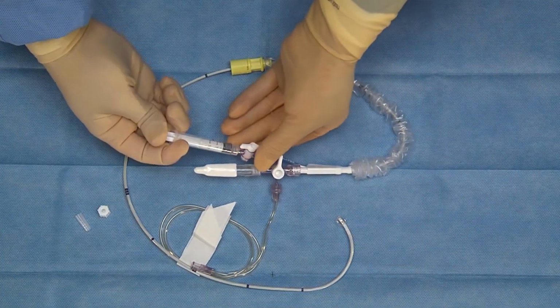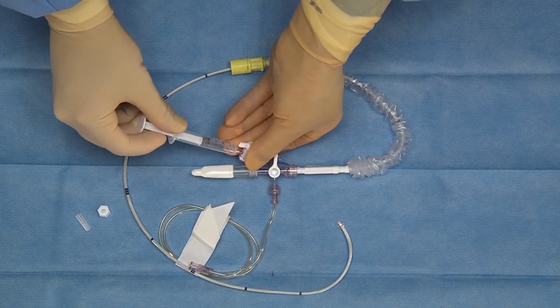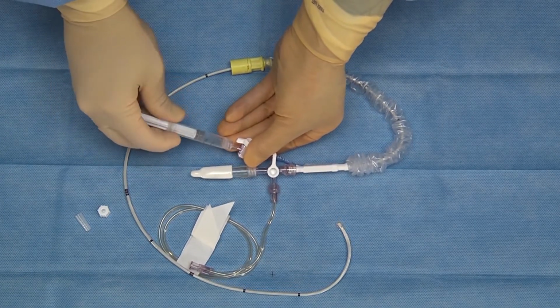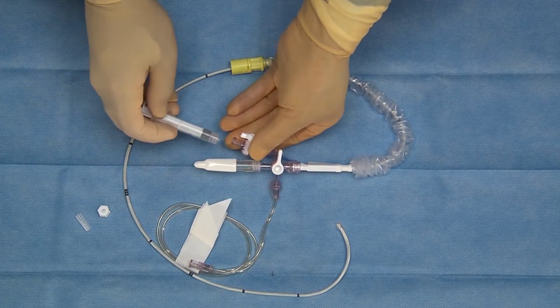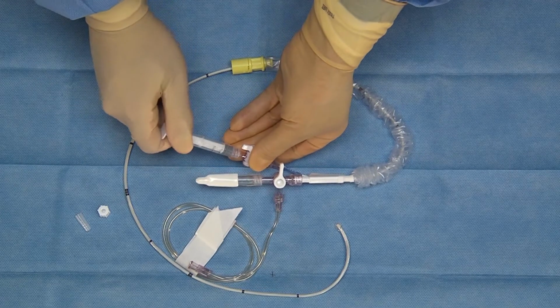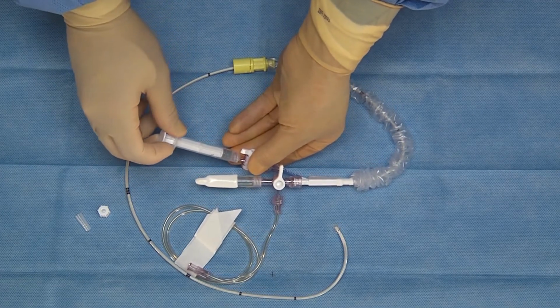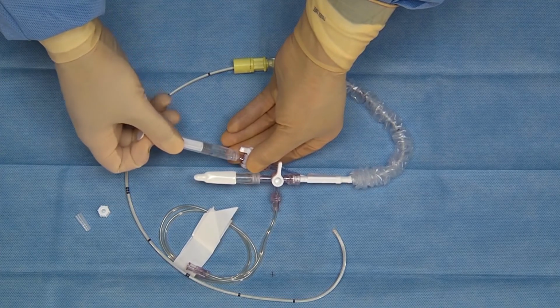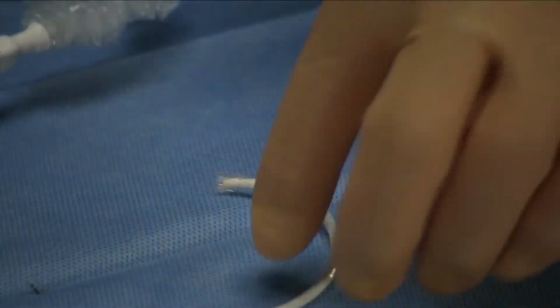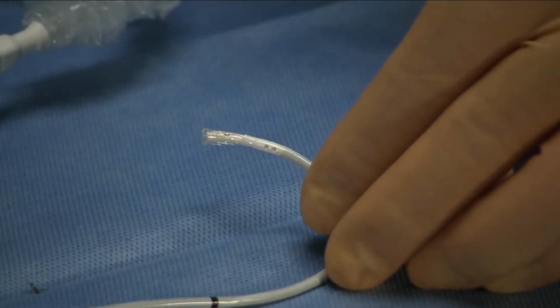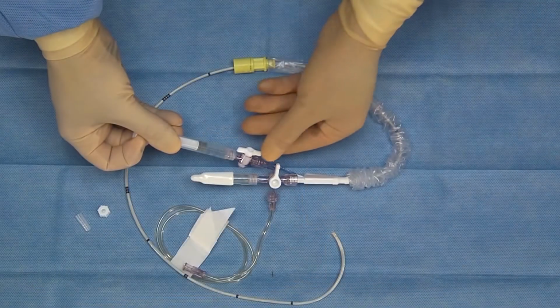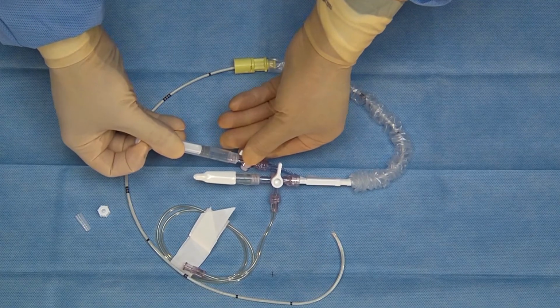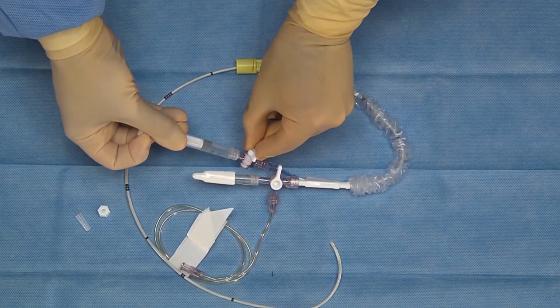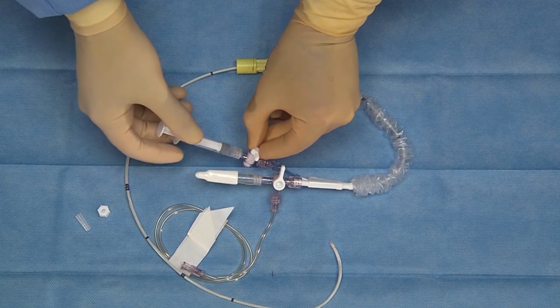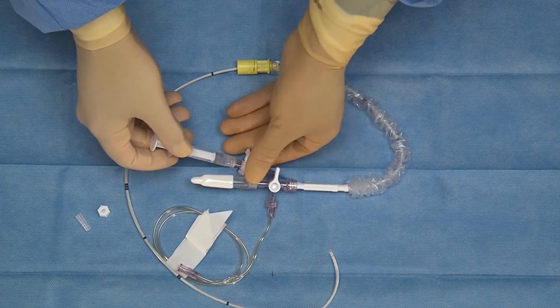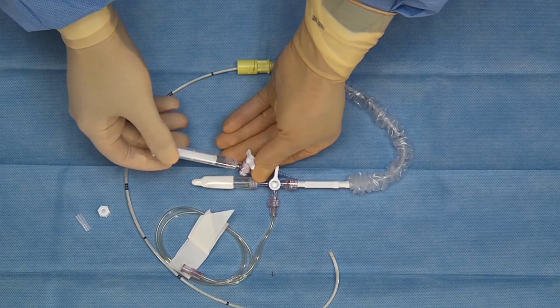Once the balloon's integrity is confirmed, draw back the syringe plunger. Remove and de-air the syringe. Reattach the empty syringe to the two-way stopcock. Draw back on the syringe plunger to ensure all air has been evacuated and the balloon is fully deflated. While the syringe plunger is retracted, turn the two-way stopcock off to the catheter, thus creating a vacuum in the balloon. This step is important to ensure the tip of the catheter passes smoothly through the introducer sheath.